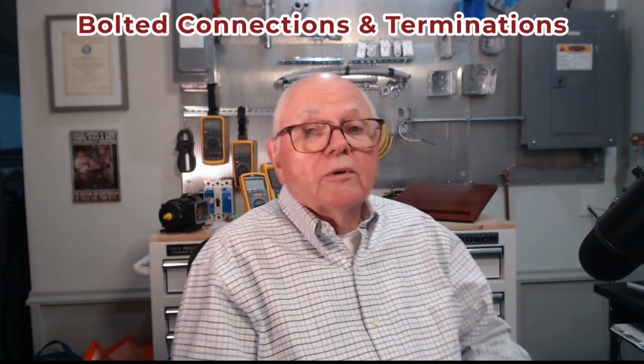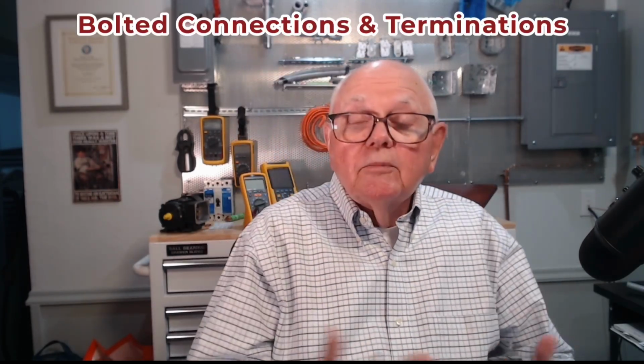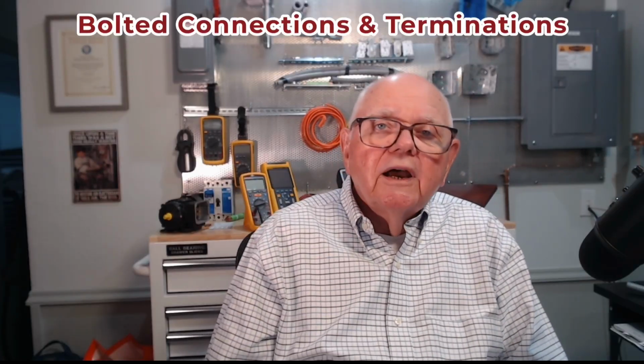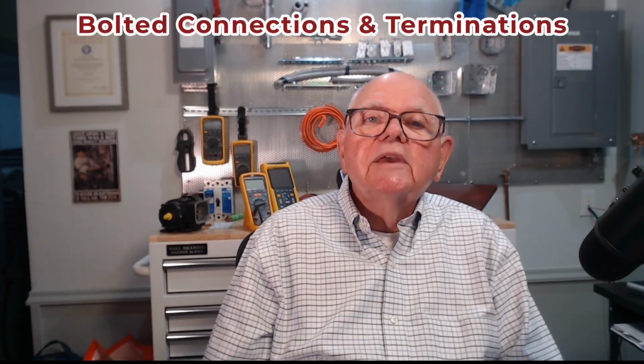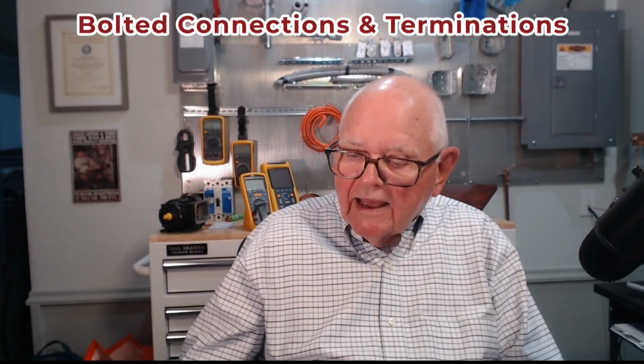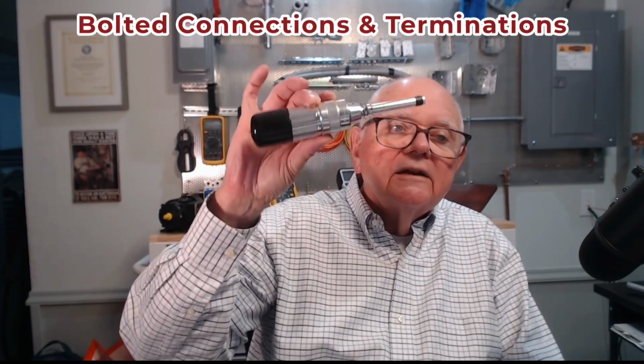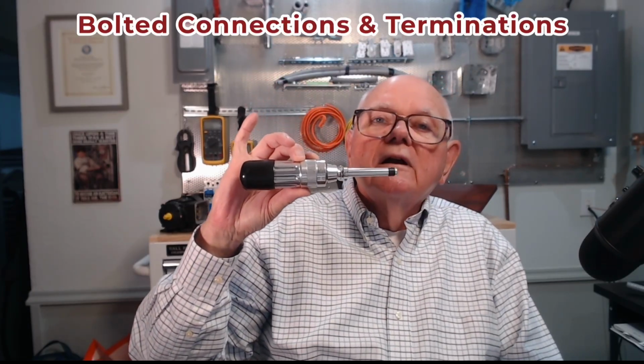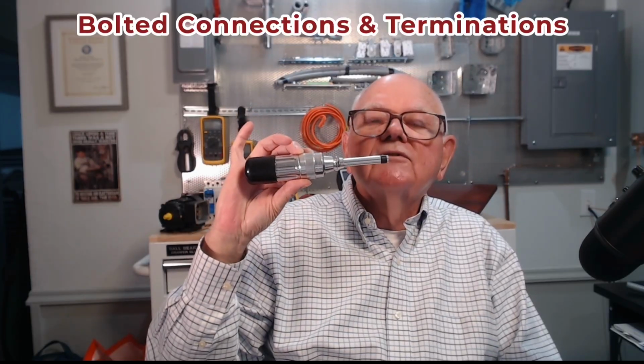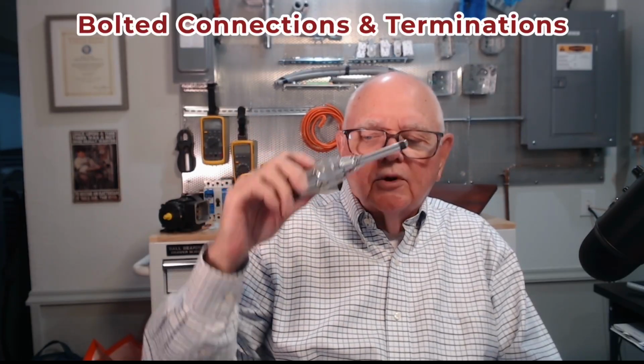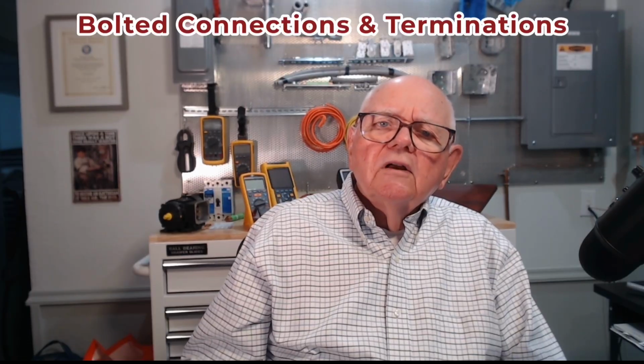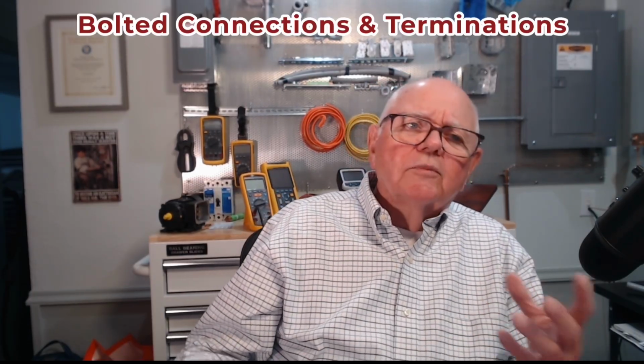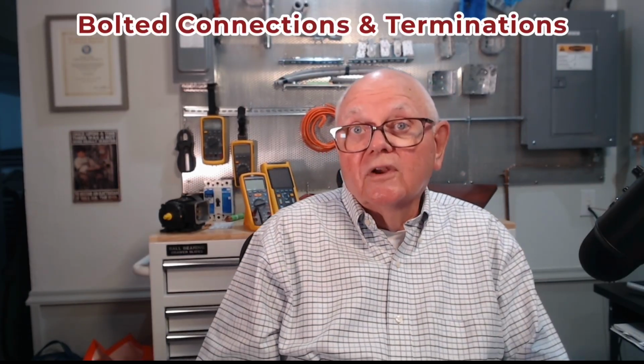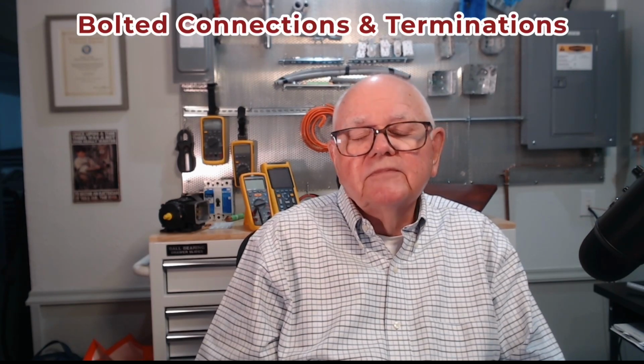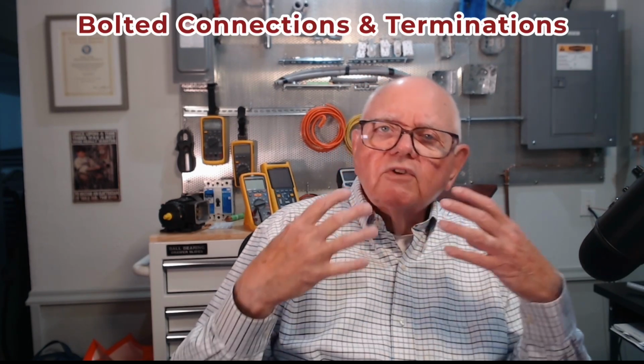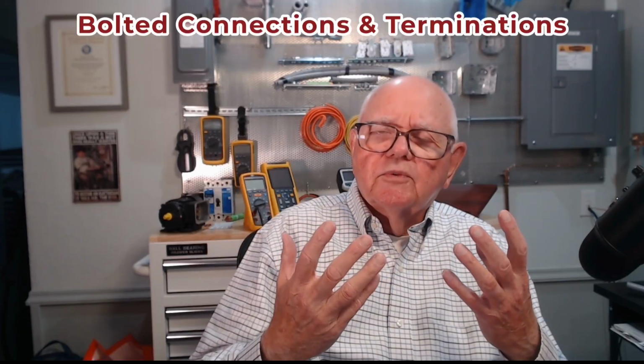So I've got a panel board back here behind me, right? And on those panel boards, as you know, the circuit breakers give me a torque requirement in inch-pounds. So I could take something like a calibrated torque screwdriver, which is going to tell me, and I can tighten those terminals to a certain torque. Now, that's important not only on the terminal screws, but on the lugs, I think is really important, where the power comes in on that panel board. Those large lugs at the top need to be tightened to a specific torque.